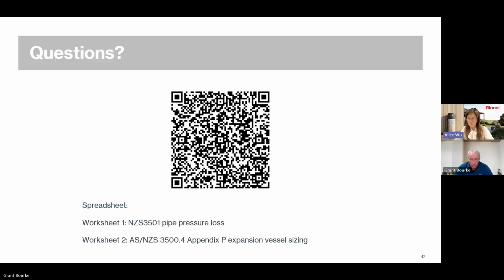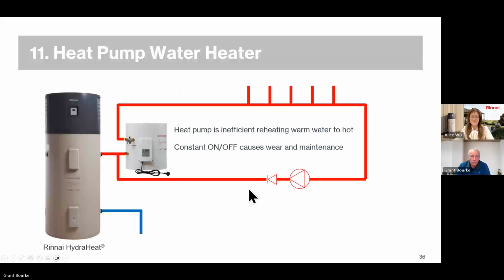Johnny, you don't want to blow colder air from one heat pump to another heat pump. Yeah, exactly. So you don't want the 2 heat pumps too close together. The Rinnai Hydra Heat draws its air from the sides and expels it vertically upwards. One of the reasons it does that is to minimize the noise, but it also means you're not firing the cold air from one heat pump into the air intake of the other one.